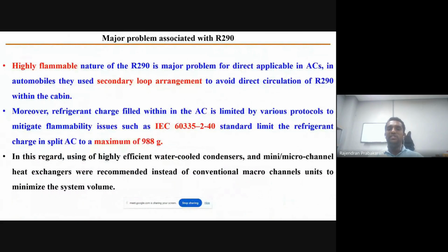But the major problem is its flammability. To mitigate this flammability issue in automobile air conditioning, they used secondary loop arrangements. They will not supply the highly flammable refrigerant propane into the passenger compartment. Instead, they used an additional loop with a brine solution to the compartment. But in split air conditioners, we need to supply the refrigerant directly into the evaporator, which is placed in the room.